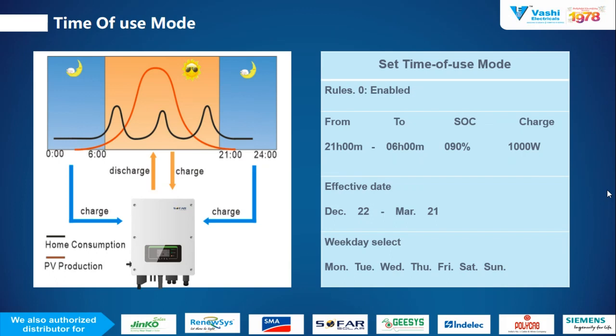So at the time when the load consumption is low, you set it to charge the battery, and in the evening time, 5 to 10 p.m., load consumption is very high, so at that time use the backup power of the battery for the load consumption. So these are the different criteria of the time management system. So it will work as a time management system in time of use mode.